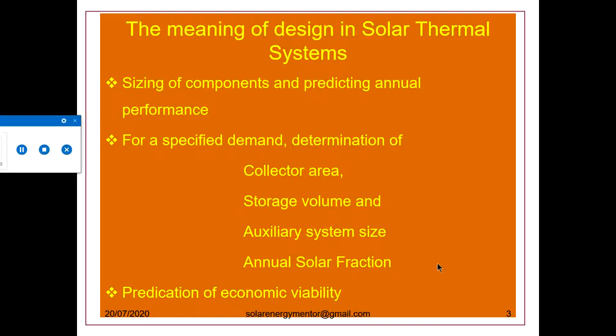When we talk of design, the meaning of design in a solar thermal system is sizing of components and predicting the annual performance. Then, for a specified demand, determination of collector area, how many collectors are required for a specified demand, what is the storage volume required, and what is the auxiliary system size required or duty on auxiliary system. And then annual solar fraction.